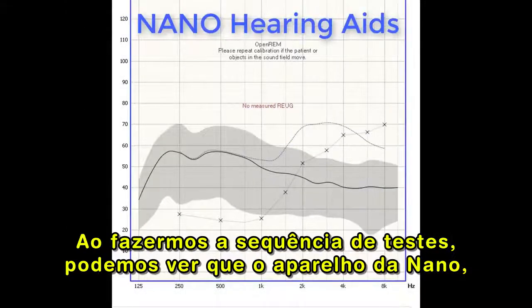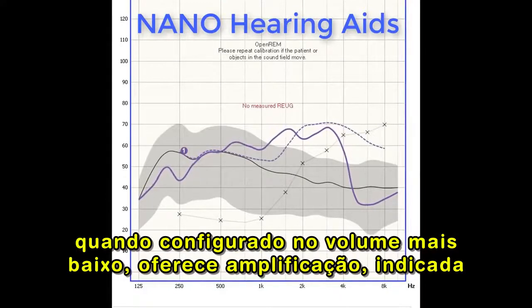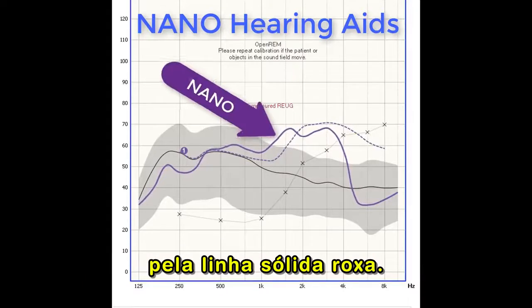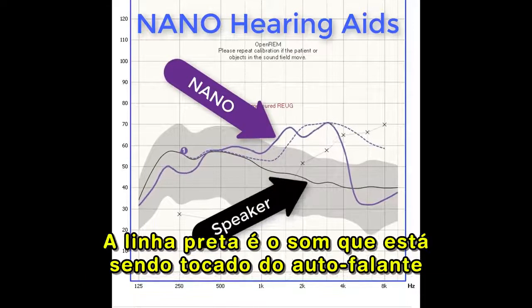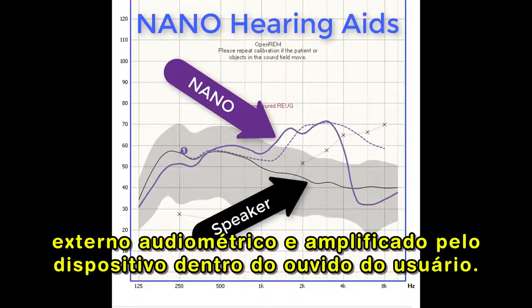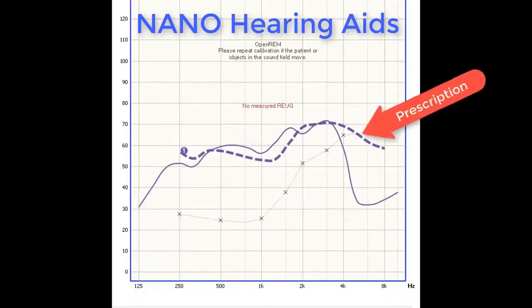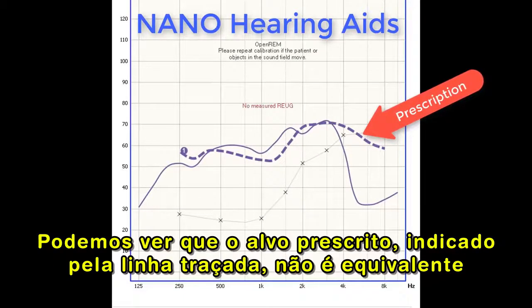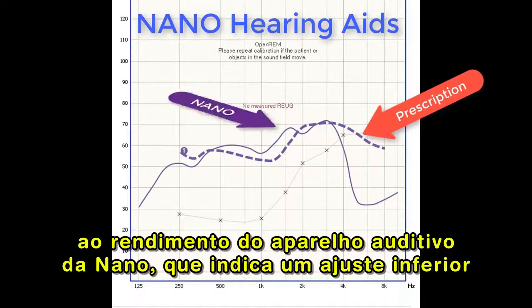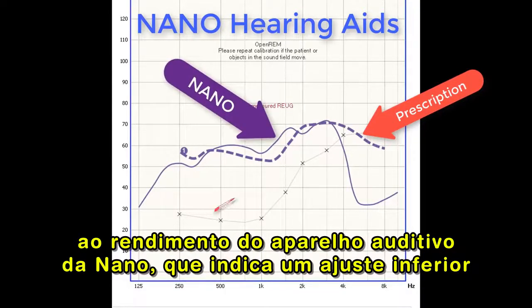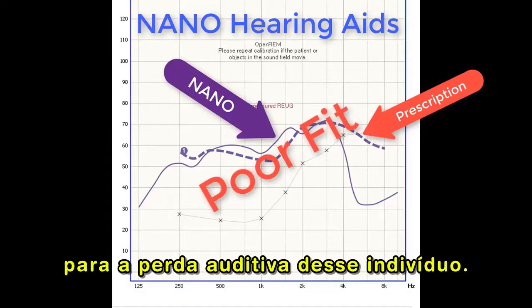As we run through the test sequence, we can see that the nano hearing aids, when set to their lowest volume level, are providing amplification, which is indicated by the solid purple line. The solid black line is the sound that is being played from the external audiometric speaker and amplified by the device inside of the user's ear. We can see that the prescriptive targets, which are indicated by the hash mark line, are not being matched by the output of the nano hearing aid, which would indicate a poor fit for this individual and their hearing loss.